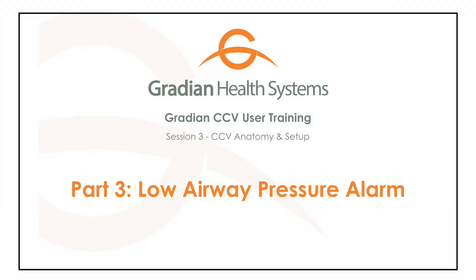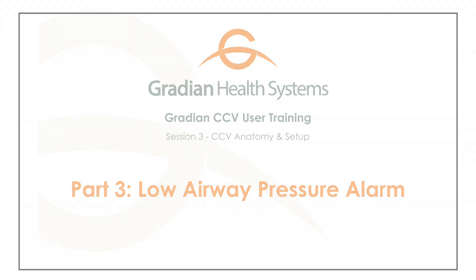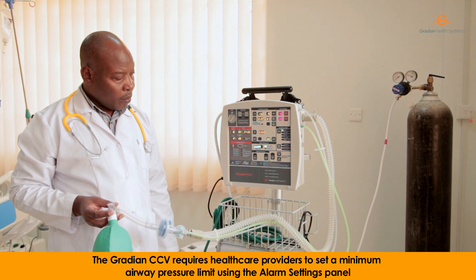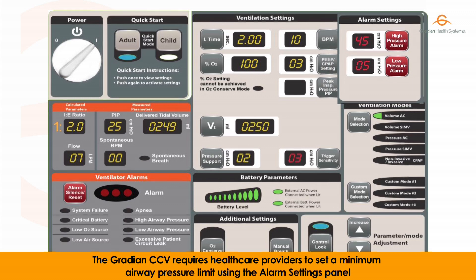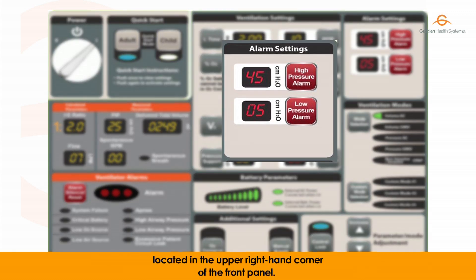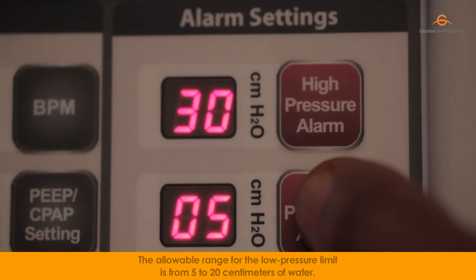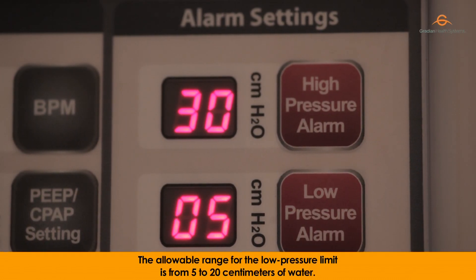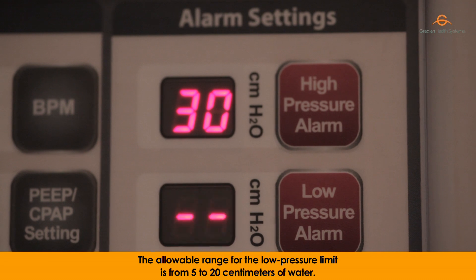Low Airway Pressure Alarm. The Gradian CCV requires healthcare providers to set a minimum airway pressure limit using the alarm settings panel located in the upper right hand corner of the front panel. The allowable range for the low pressure limit is from 5 to 20 cm of water.